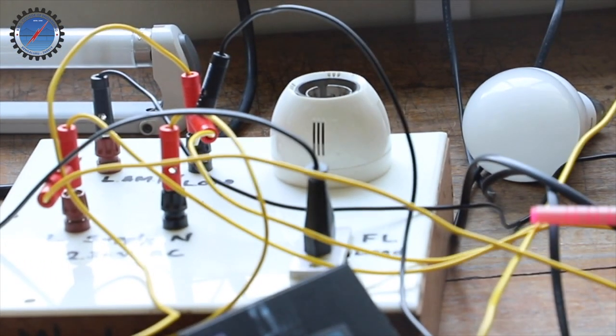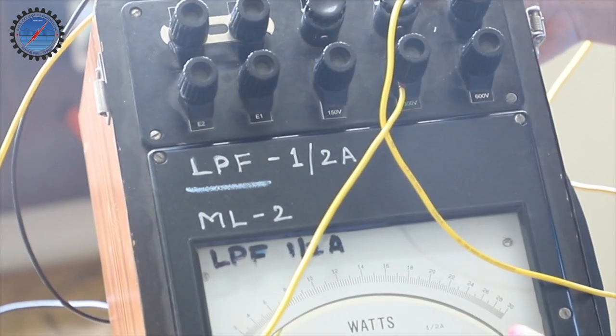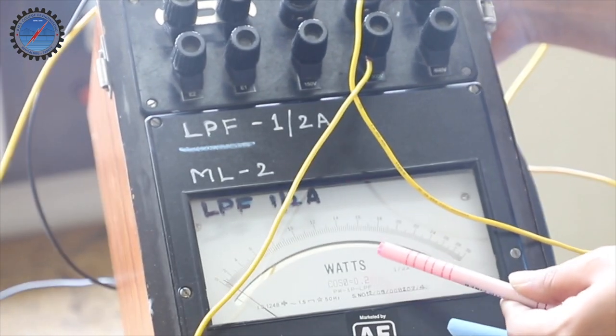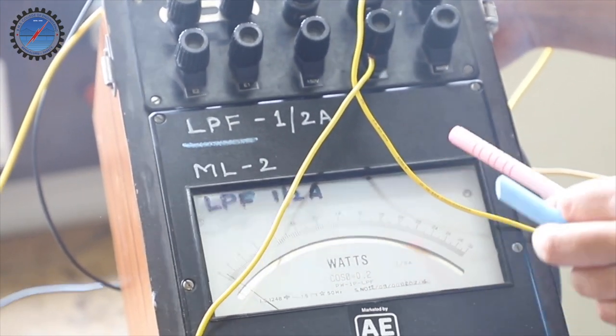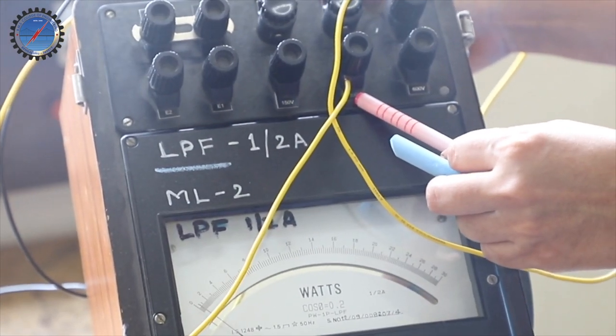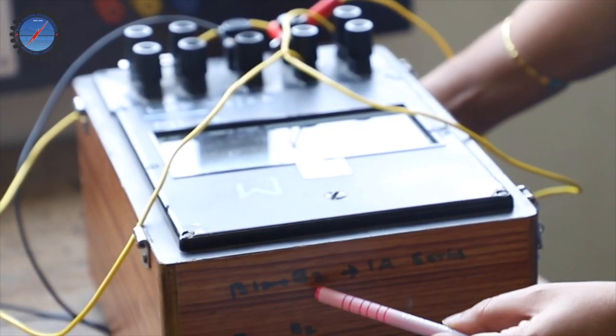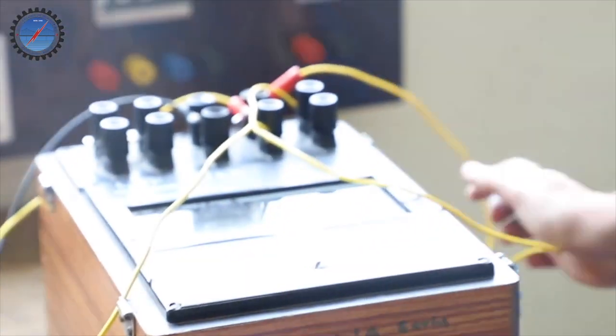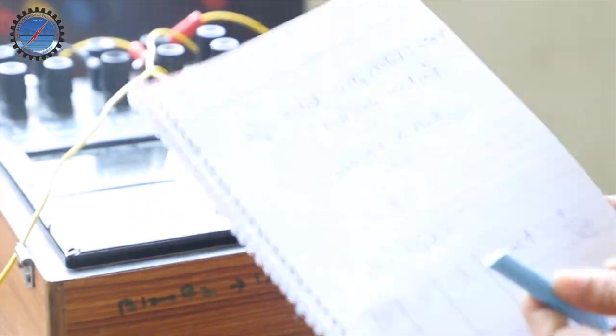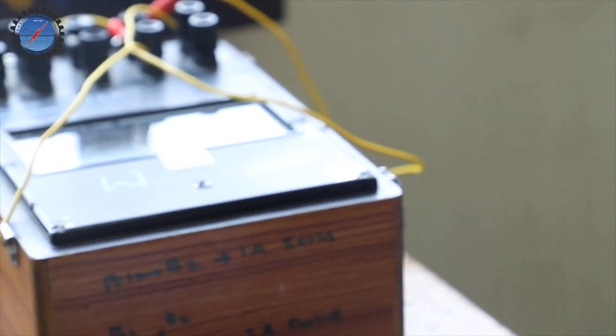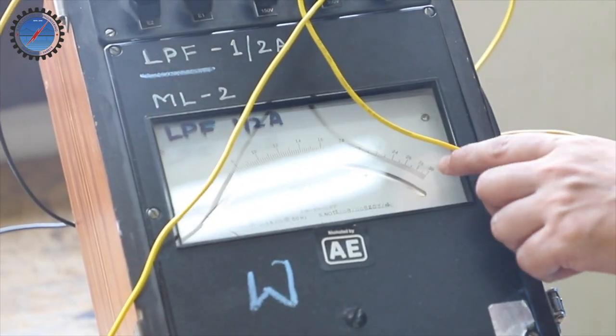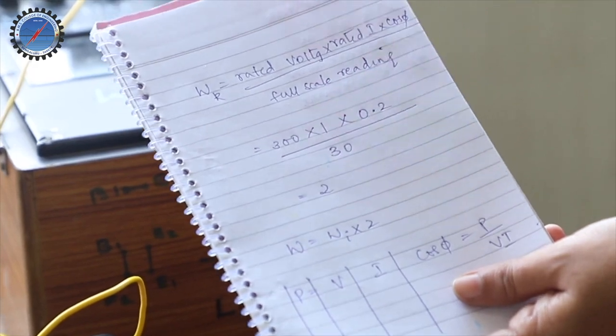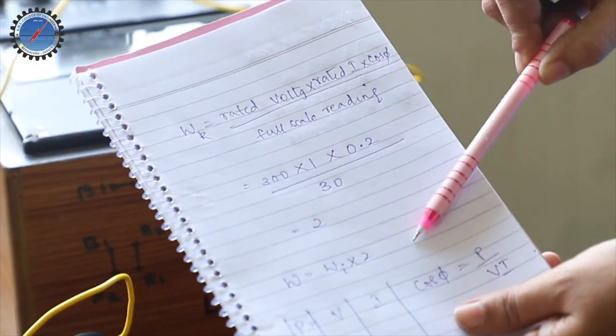First, we calculate the wattmeter constant. This is an LPF — low power factor — wattmeter, since we have taken an RL load. The cos phi of this instrument is 0.2. The rated voltage selected is 300 volts, and the rated current with B1 and B2 connected is 1 amp. The full scale reading is 30 divisions. Substituting these values, the wattmeter constant comes out to be 2. Whatever the wattmeter indicates must be multiplied by 2 to get the exact power consumed.